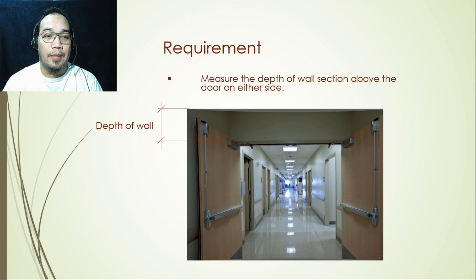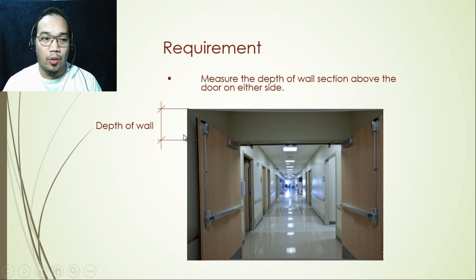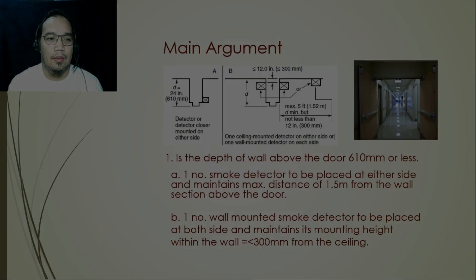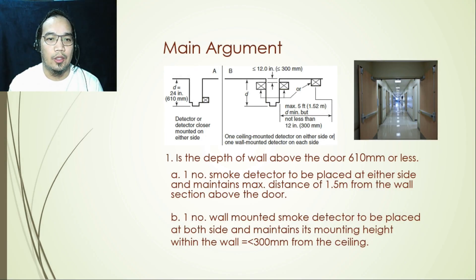The key requirement when providing a smoke detector designed to release a fire door is that you need to know the depth of the wall above the door. This is the part of the wall where we measure from the underside of the ceiling down to the bottom of the wall above the door. Once we have determined this depth, we can proceed with the placement rules.